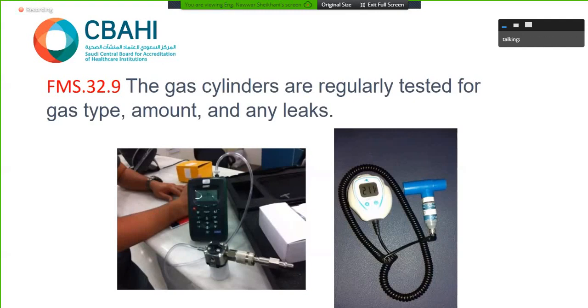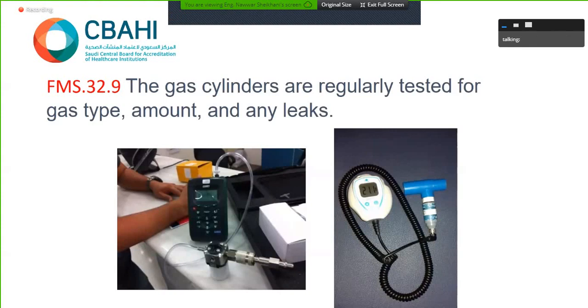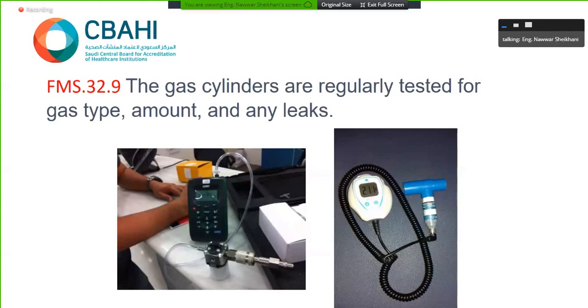However, after 1 week, we received an appreciation letter from the factory stating, thank you so much. We sent our tools to Italy for calibration, and we found the percentage you told us is correct. We are very sorry. So based on that incident, standards were put based on actual incidents. Since then, we have added this condition that once you receive a batch of cylinders, please use at least an oxygen analyzer to measure or to identify the type of the cylinder.